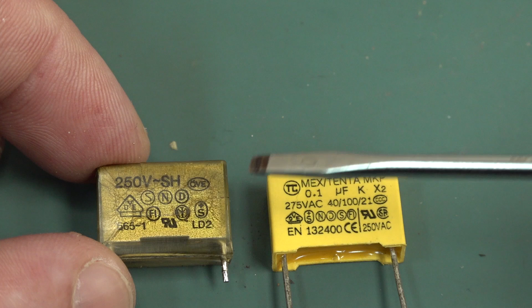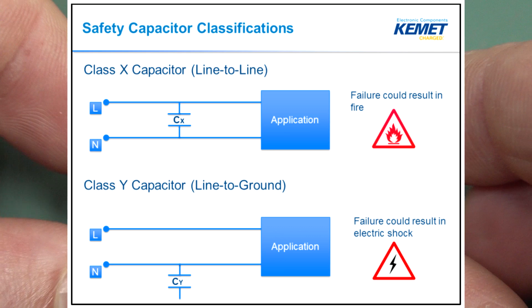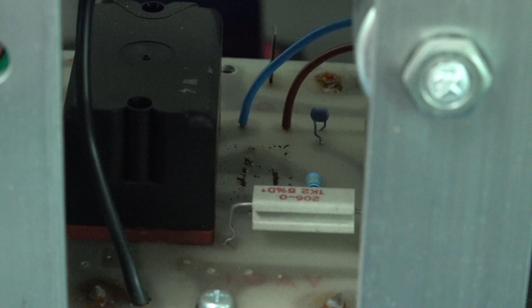Now, you can actually use a Y-class cap in the X configuration, but you can't, or shouldn't, use an X-class cap in a Y-class configuration. It's just a safety thing. You can see some ooze down there on the board - that's just spewed out the bottom of that cap. We'll just clean that off before we put a replacement in.